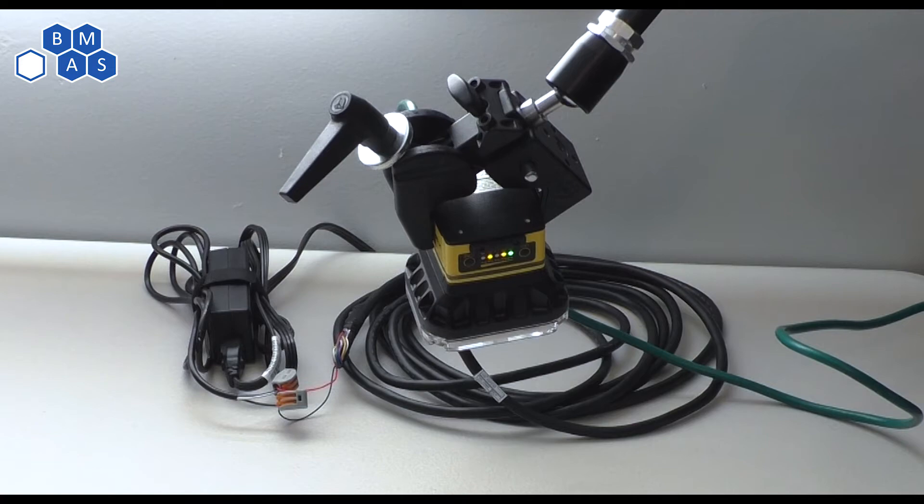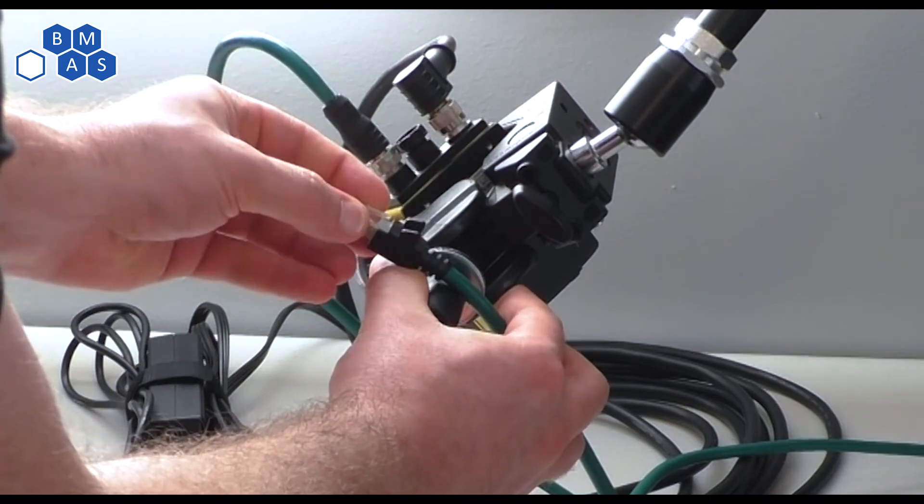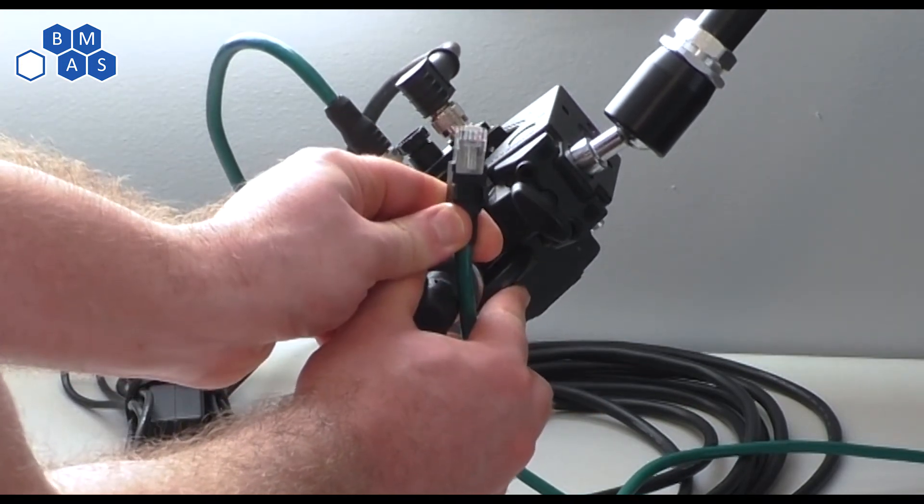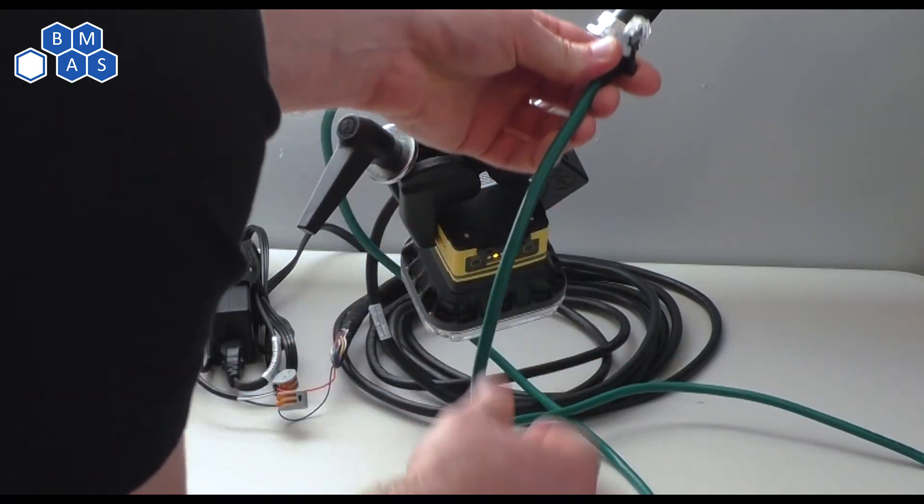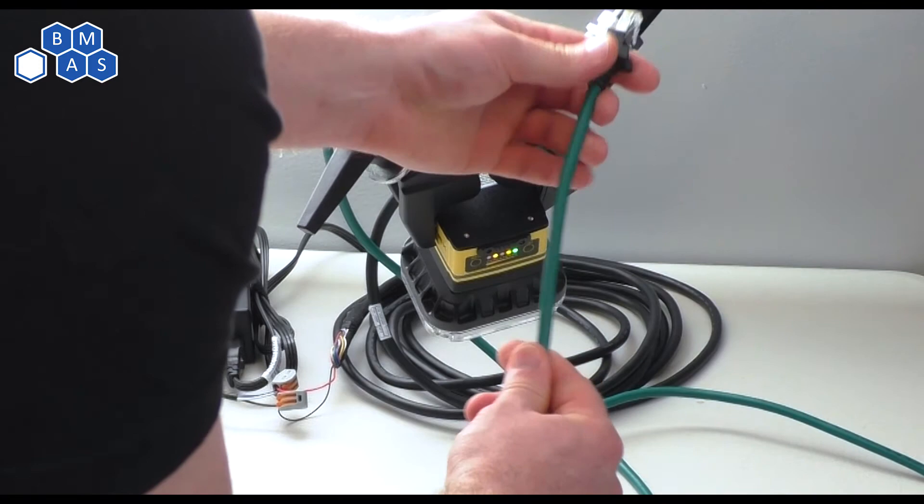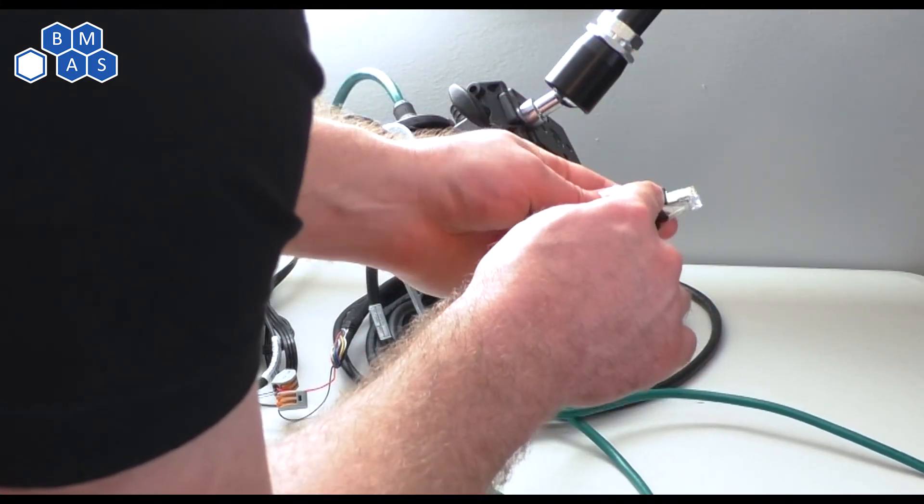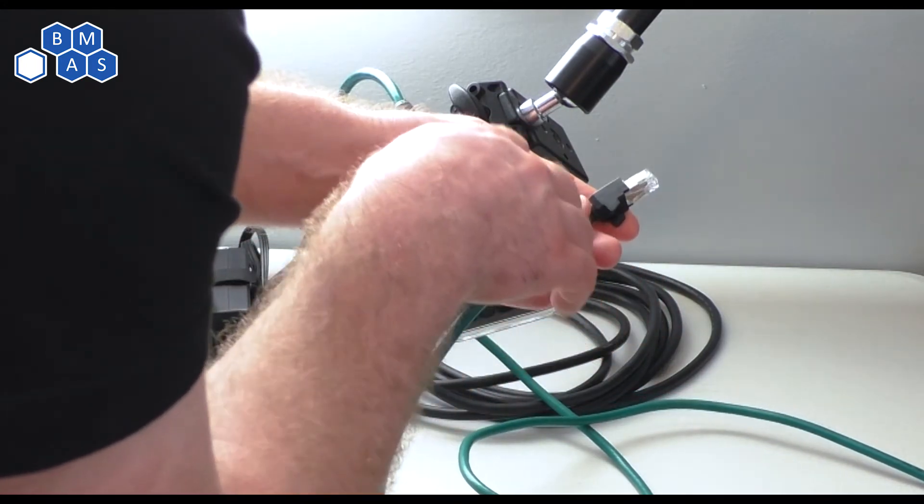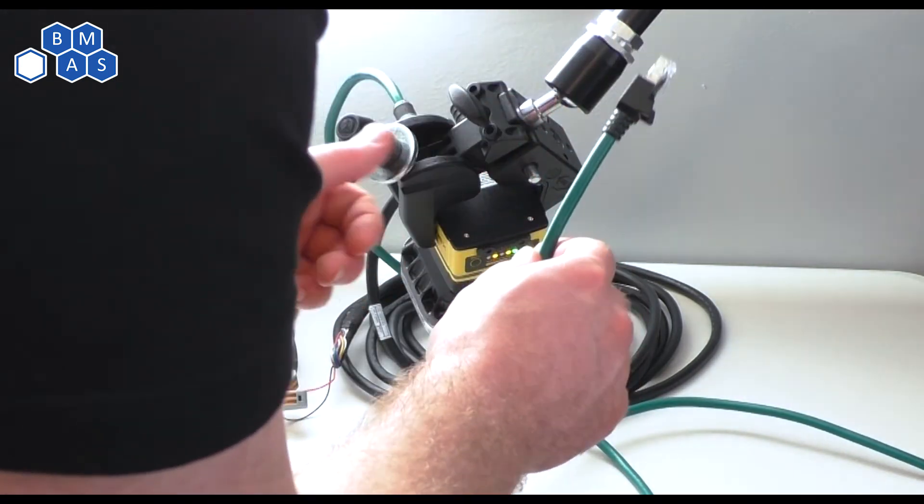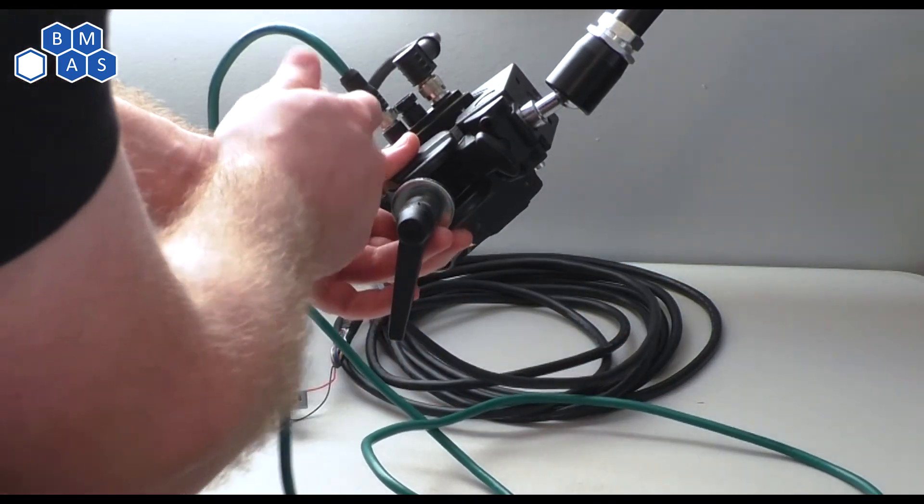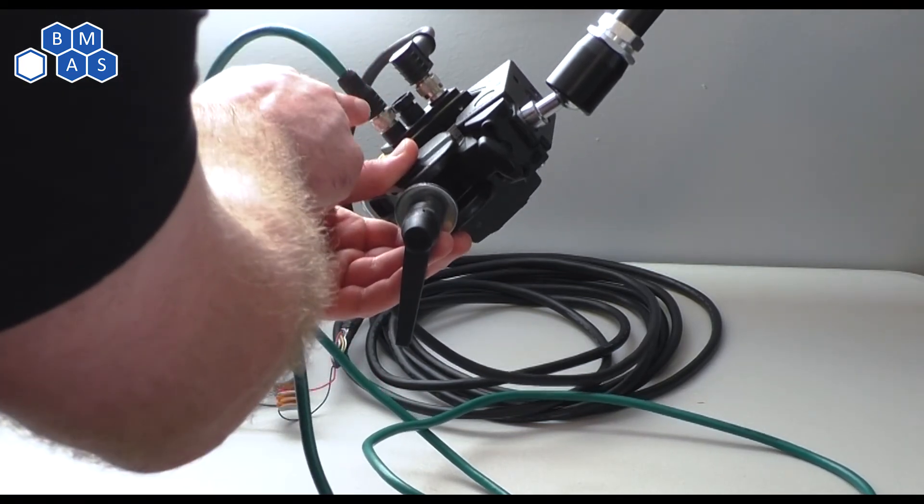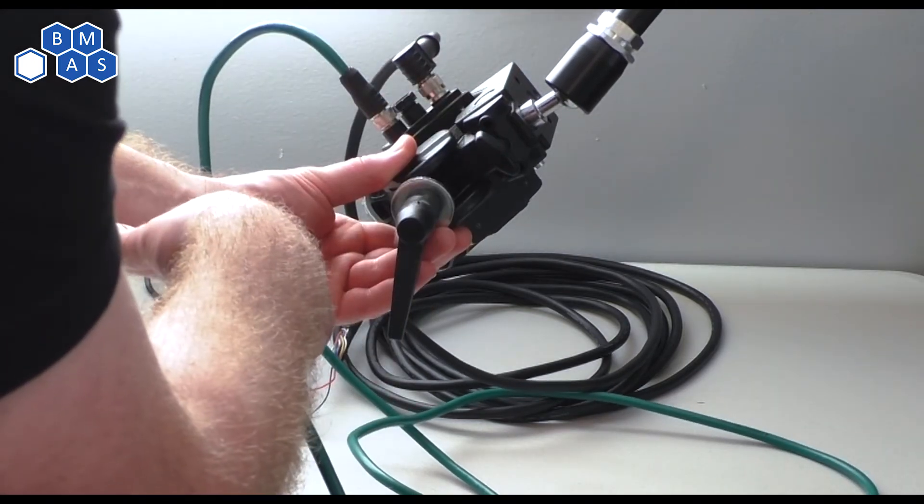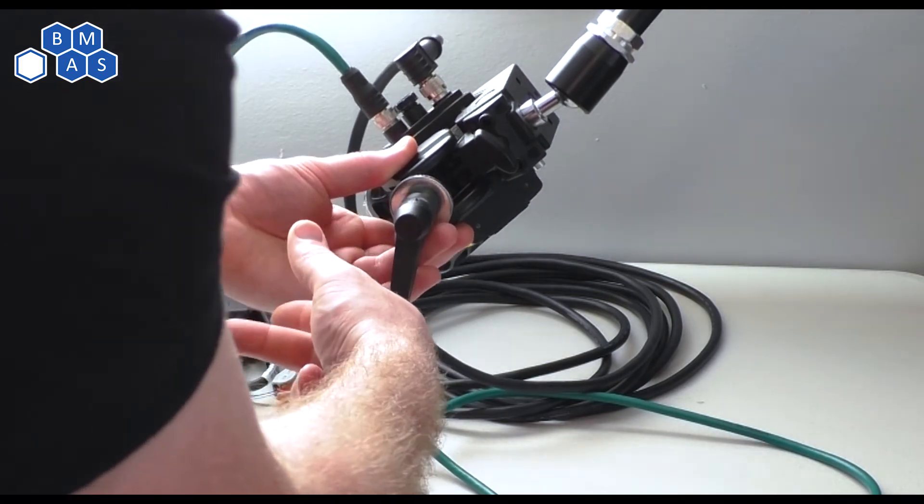I also want to talk about this Ethernet cable specifically. This is an industrial Ethernet cable. So it comes with this round end instead of just the RJ45 end that you're used to seeing in office environments or on your laptop. But beyond that, this is also an industrial rugged cable. And you might not just know it by looking at it, but here on the end, you can actually see some of the shielding that they have in here. This is more shielded and more robust than what you would normally see in an office environment. Another good thing to point out, just to pay attention to, I've got an example of a right angle connector here and a straight connector. And depending on where you mount this on your machine, you'll probably have a preference for one over the other. So just be aware that that exists.